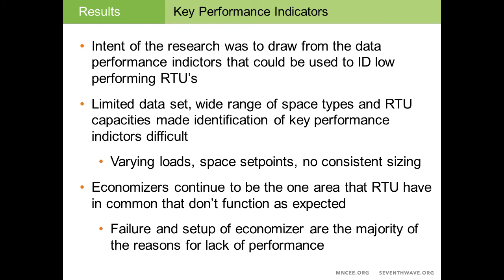But one thing that did come out of this was that economizers continue to be a problem, and this is consistent with what other researchers have found across the country, that economizers fail due to lack of maintenance. They even fail because they're not set up appropriately. They have the inappropriate set points that don't allow them to economize. So I think that pretty much wraps up the monitoring phase of things. I'm going to hand it back to Scott, and he'll close this out.